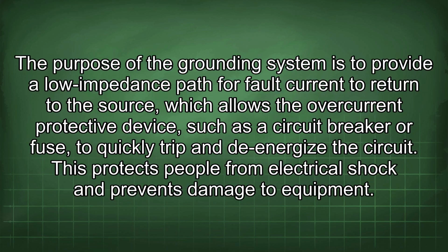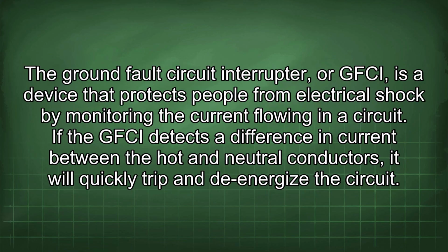tamper-resistant outlet. The purpose of the grounding system is to provide a low impedance path for fault current to return to the source, which allows the overcurrent protective device, such as a circuit breaker or fuse, to quickly trip and de-energize the circuit. This protects people from electrical shock and prevents damage to equipment. The ground fault circuit interrupter, or GFCI, is a device that protects people from electrical shock by monitoring the current flowing in a circuit. If the GFCI detects a difference in current between the hot and neutral conductors, it will quickly trip and de-energize the circuit.